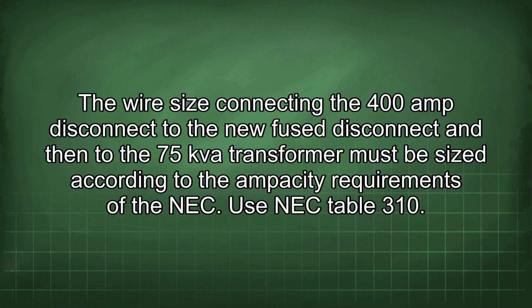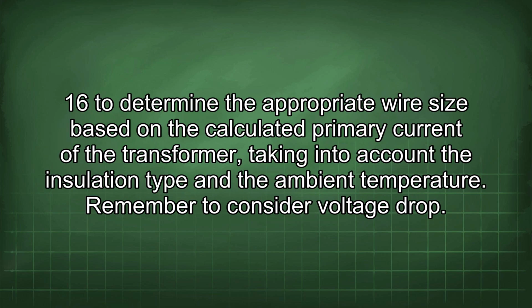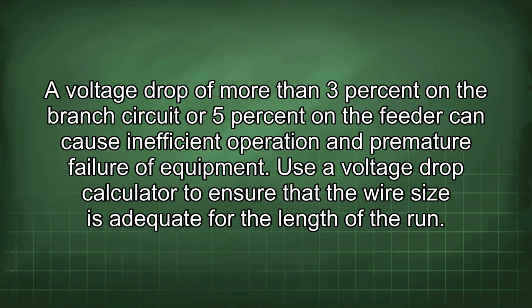The wire size connecting the 400 amp disconnect to the new fuse disconnect and then to the 75 kVA transformer must be sized according to the ampacity requirements of the NEC. Use NEC Table 310.16 to determine the appropriate wire size based on the calculated primary current of the transformer, taking into account the insulation type and the ambient temperature. Remember to consider voltage drop. A voltage drop of more than 3% in the branch circuit or 5% on the feeder can cause inefficient operation and premature failure of equipment. Use a voltage drop calculator to ensure that the wire size is adequate for the length of the run.